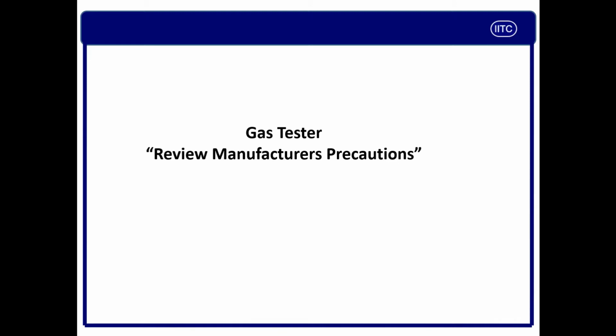And next is if LEL is more than 100, then sampling may provide wrong LEL reading. If it is already 100% plus, then definitely you are not able to get correct LEL readings. And last but not least is do not remove instrument from its case when in a hazardous environment. So guys, just to summarize, you have understood the precautions that manufacturers are giving. This depends on manufacturer to manufacturer.